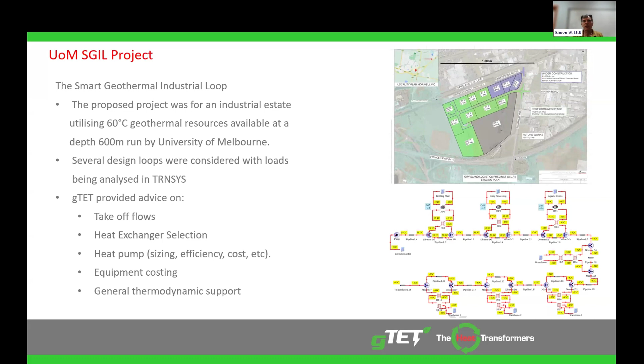Okay, so the results, just one slide on the results from this project. There were two basic concepts: one was the direct single pipe, and the other was the indirect double pipe. The indirect double pipe is like your traditional ring main type system. The direct single pipe, because you have to re-inject it, you want to transport the water to another location if possible, rather than doing angled drilling and all that sort of stuff. Not my area of expertise, but I was a bit skeptical about the direct single pipe because consumers aren't re-injecting, but returning the cooler water back to the main heat pipe, so the downstream consumers have to add more heat to boost their system.